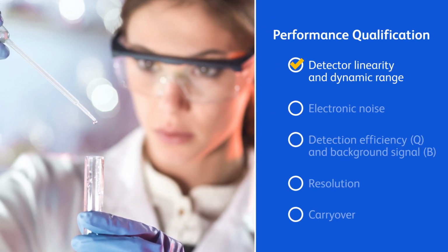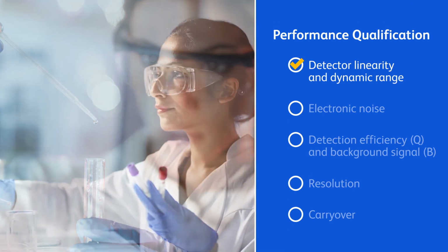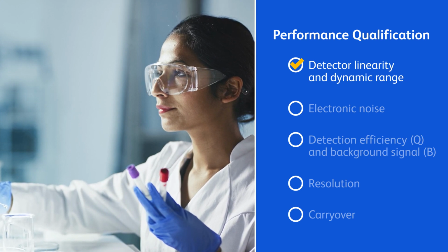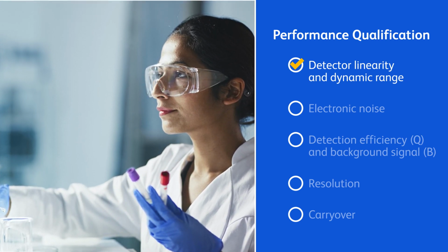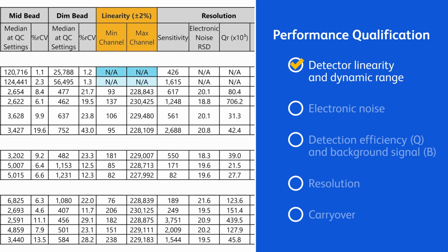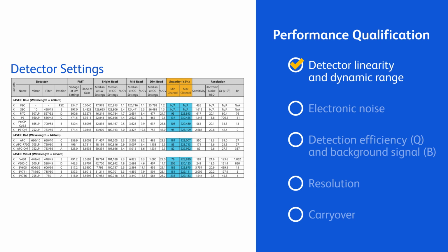Detector linearity can be assessed using multi-intensity hard-dyed beads by plotting the fluorescence intensities associated with different bead populations versus the ERF or MESF values. BD FACSLyric uses a ratiometric method to calculate detector linearity for each fluorescence detector using BD CS&T beads, which is the ratio of different CS&T beads across the detector range.